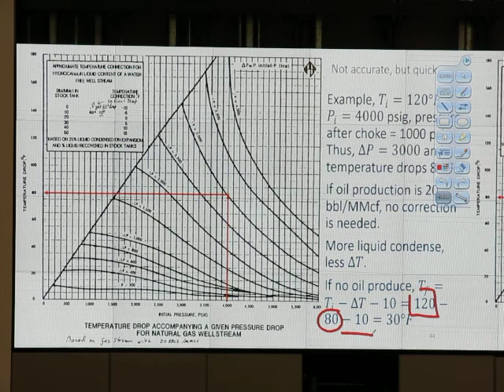Is it production of liquid in general, or water versus oil, or just total? The chart says approximate temperature correction for hydrocarbon liquid content of water. I think for this chart it just says liquid in general. But from my point of view, I look at Cp, which is heat capacity. The heat capacity of water, I just Googled, is about 4,182 joules per kilogram. For oil, it's about 1,800 or 2,000 joules per kilogram. For natural gas, it's about that much, or maybe a little bit less.